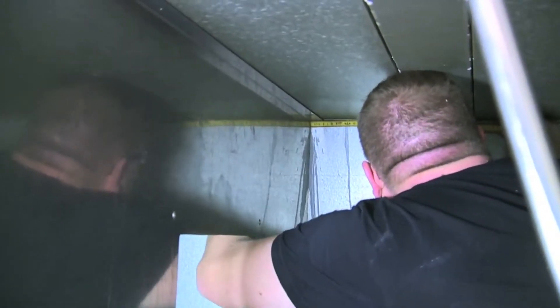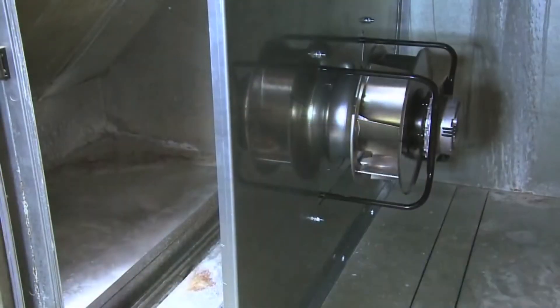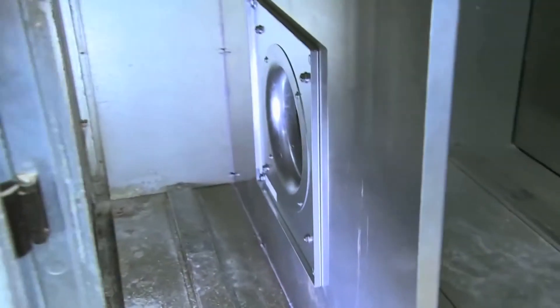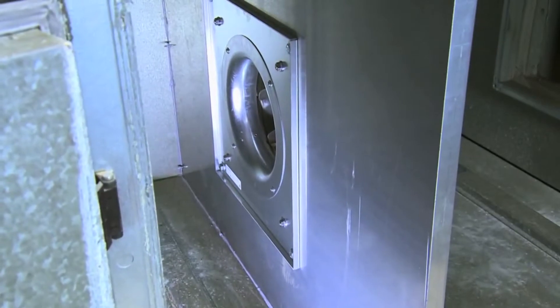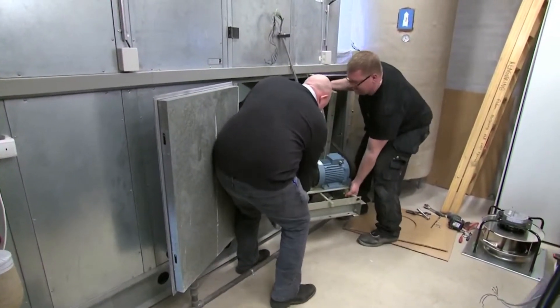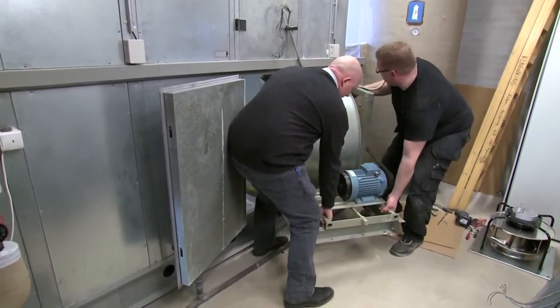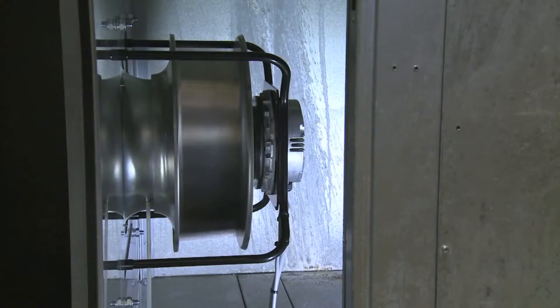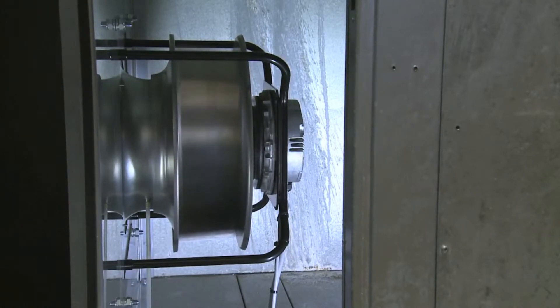Minimum separation distance requirements must be met, but since the new fans are so compact, there is normally always room for them. This energy-saving technology means that it can pay off to remove the old belt-driven fans in about 70% of all ventilation systems by replacing them with a new EC fan, which translates into a 30–70% saving.